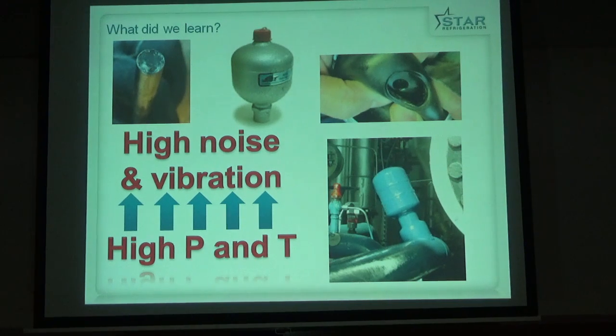It was about 125 decibels at 1 meter from the compressor, and by adding the Helmholtz resonator we reduced that to 98, 99, so reduced by over 25 decibels the noise level coming off the compressor. So again, fantastic learning process, but it was a bit painful getting there.